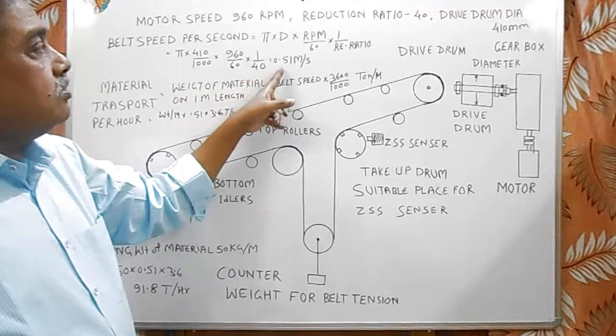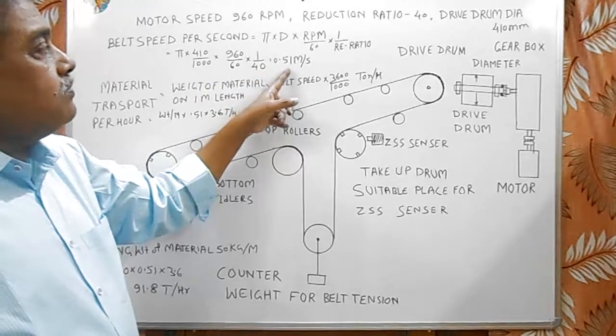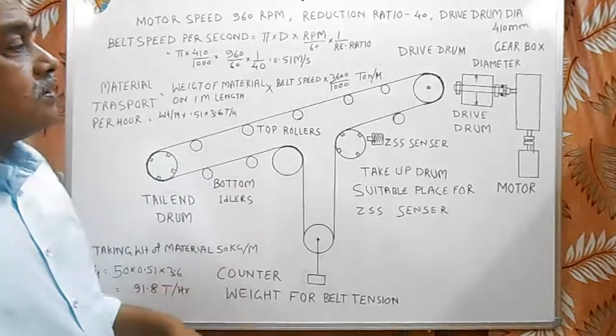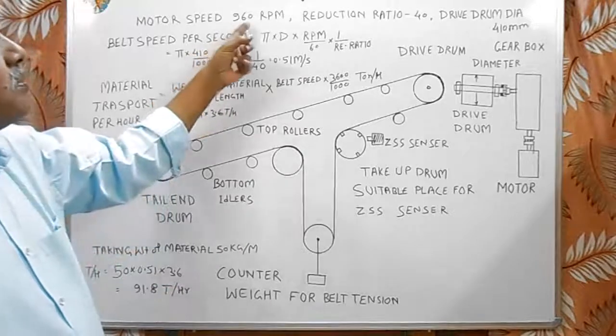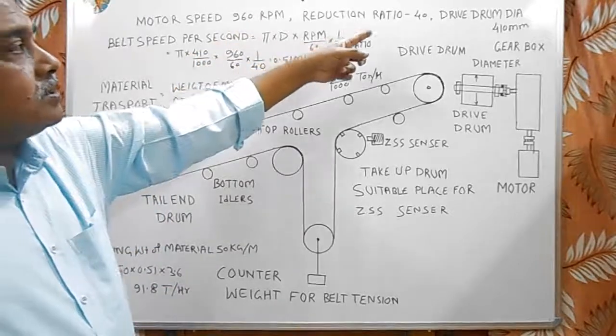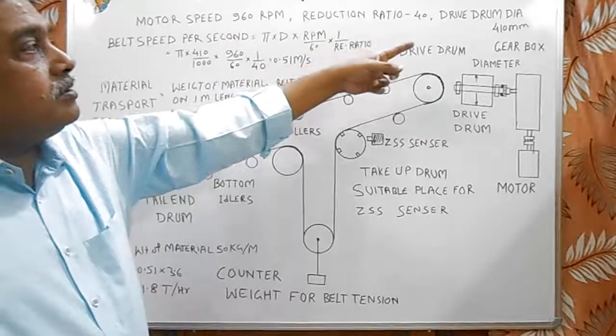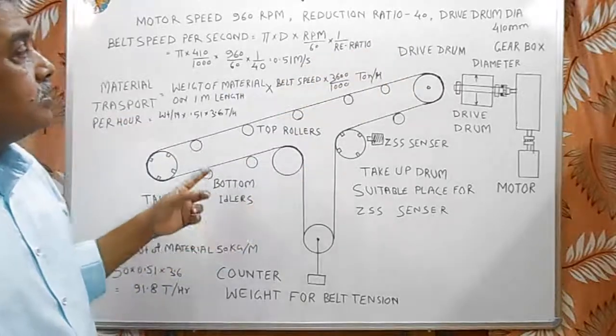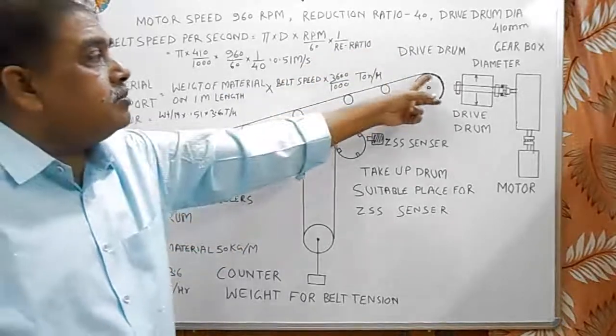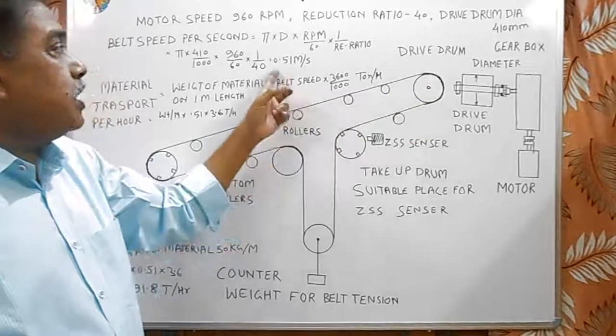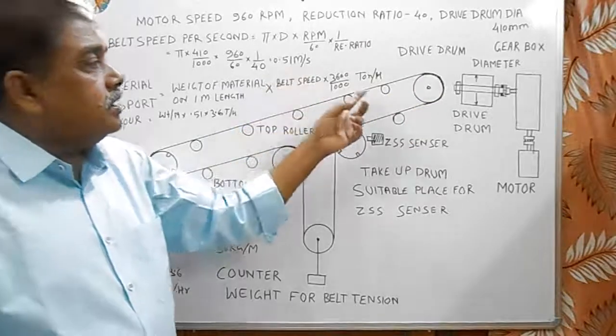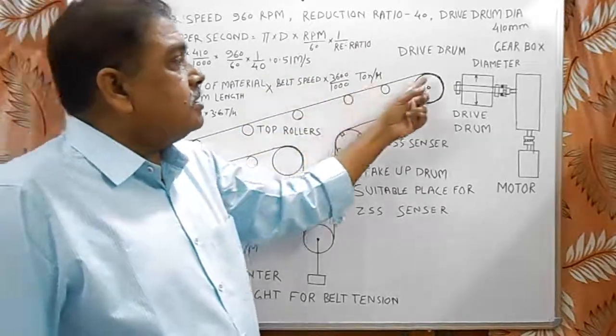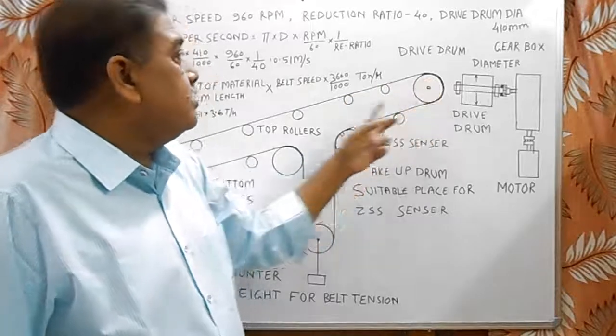It is equal to 0.51 meters per second. Means with this motor of 960 rpm, reducer ratio of gearbox 40 and drive drum diameter is 410, the linear speed of drive drum surface is 0.51 meter per second. And the belt speed is same as the linear speed of drive drum.